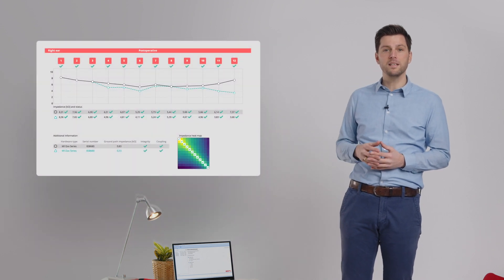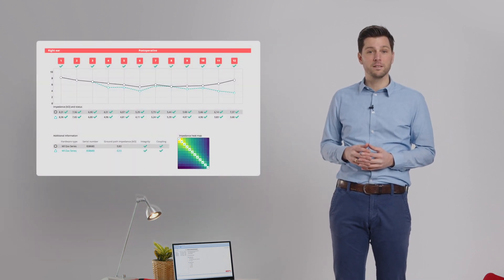Maestro 10 has a new user interface for implant telemetry to streamline how you review the data. Now, all of the information you need is on one screen, with a new intuitive impedance heatmap that you will get with every single measurement, no matter which MED-EL implant your patient has. This will make it easier for you to quickly evaluate the impedance status across the entire electrode array, and to compare it to previous heatmaps.